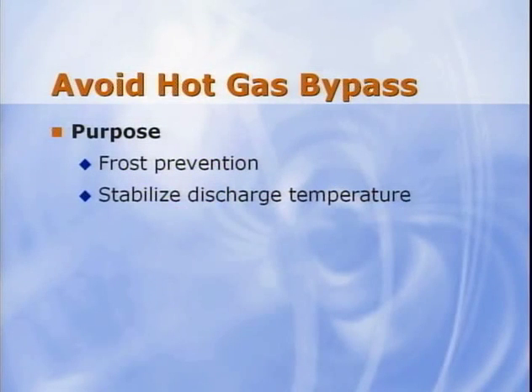Hot gas bypass was traditionally used on VAV systems at low airflow, low tonnage conditions to prevent frosting of the evaporator coil while the VAV controller allowed the compressors to cycle off through time delays. One of two things happened. Either the hot gas was literally set to prevent frosting, in which case it never came on because the suction pressure never got low enough to activate it, or it was set so high that it was activated quite frequently and affected the capacity of the unit at many operating conditions.